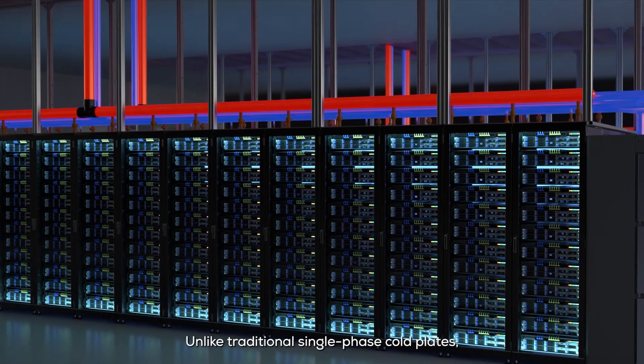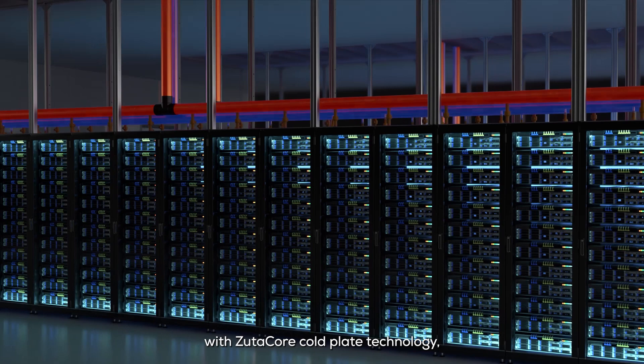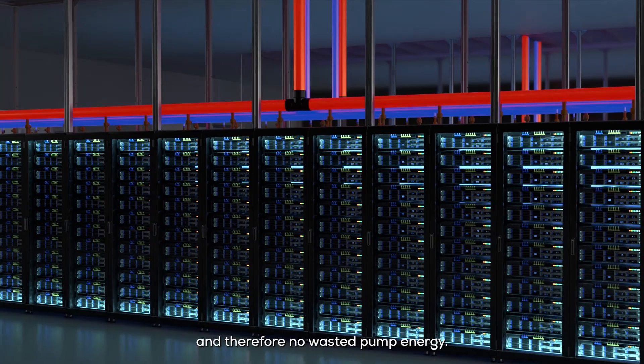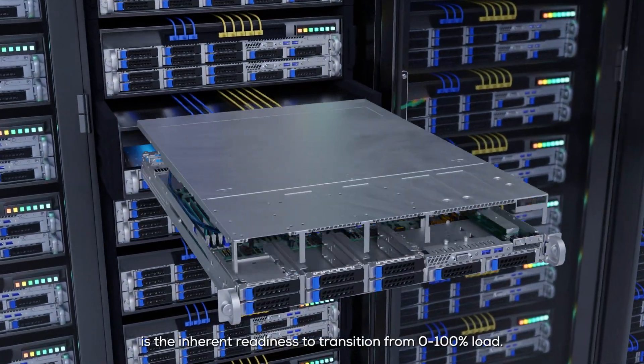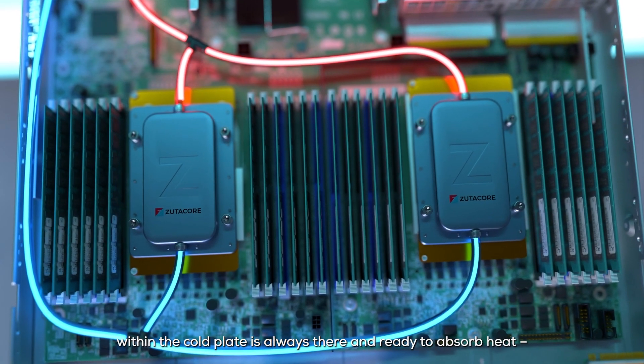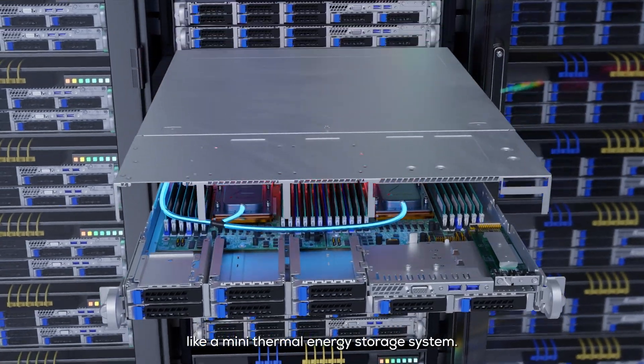Unlike traditional single-phase cold plates where the liquid flow remains constant regardless of load, with ZutaCore cold plate technology, when there is no load there is no flow and therefore no wasted pump energy. An additional benefit is the inherent readiness to transition from 0 to 100% load — the pool of heat transfer coolant within the cold plate is always there and ready to absorb heat, like a mini thermal energy storage system.